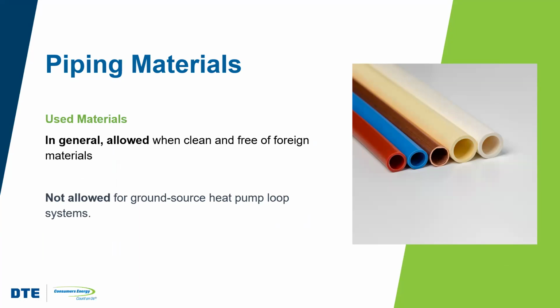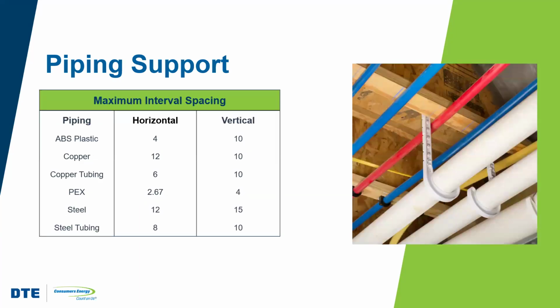Very interestingly, I thought this was really interesting. Used pipe and fittings can be employed in a new system, as long as they're clean. There's no debris, there's no foreign materials, except with ground source heat pump piping. Those have to be brand spanking new. But otherwise, we can actually use used materials, which may come in handy, particularly now when costs are so high.